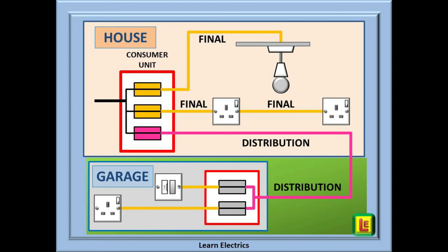Now we can put in the sockets and switches needed in the garage, and because they are the last leg again, they are all final circuits — so let's mark these in orange. We have shown a fused spur here as part of a final circuit. This is correct. Although the fused spur or fused connection unit contains a fuse, it is not considered as a marker between a final and a distribution circuit. Cables going into a fused spur are part of a final circuit.